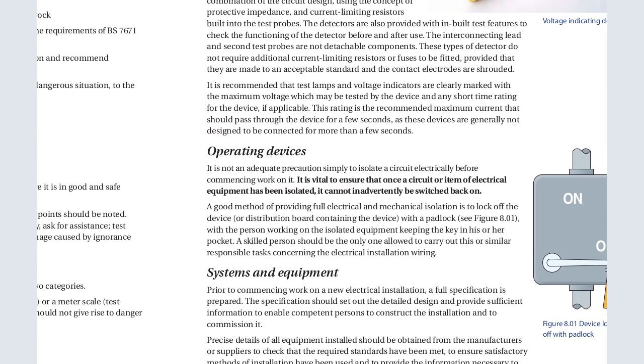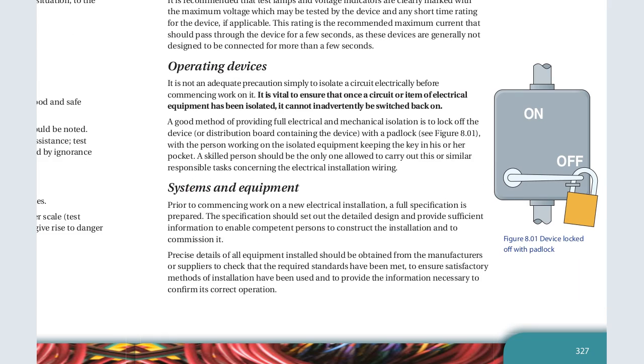And then we go down to protective devices. Now, what happens on the protective devices? It is not adequate precaution simply to isolate the circuit electrically before commencing work on it. It is also vital to ensure that once a circuit or an item of electrical equipment has been isolated, it cannot inadvertently be switched back on. So some of the things that are normally done are that protective devices like the circuit breakers or the fuses are pulled out. You pull out or you tag out, you lock the power supply so that nobody can tamper. So that at any time when you are doing the test and inspection, nobody can come and put on the power without your knowledge.